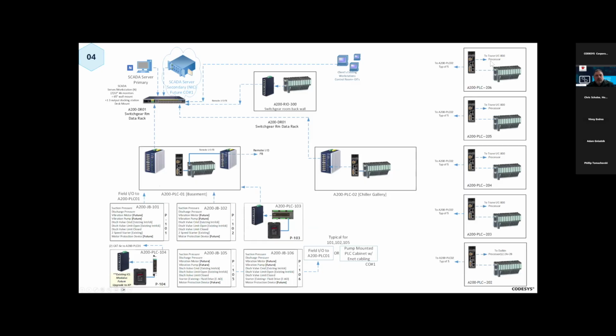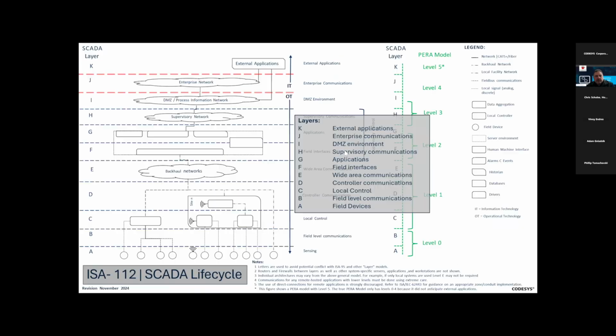So we have chillers that we have objects written. We'll show you with chiller blocks for a couple different vendors that they happen to have. We made faceplates for them. The processor on board, while it's communicating to the processor of the chiller, it's also doing the control of the chiller as well as the ancillary flow, temperatures, pressures, and that. And then they all communicate back up to a layer processor that's doing some of the balance of plant control. We're doing energy optimization on pumping systems, chilled water condenser systems, power controls. These pumps range, and we'll talk a little bit about it, anywhere from 800 horse down to 200 horse.